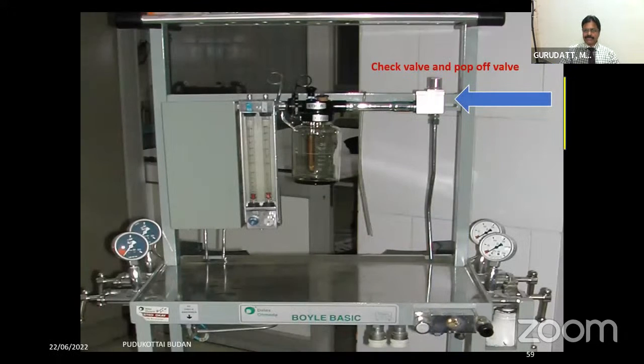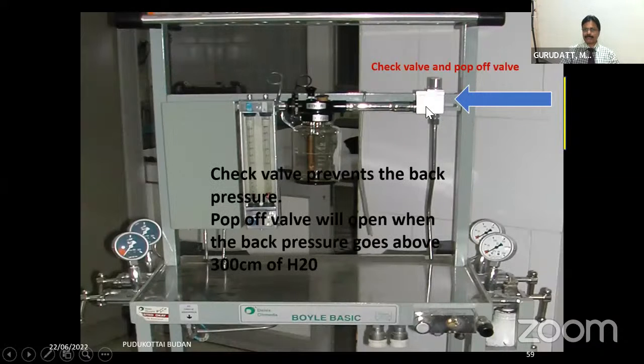After the back bar, in the majority of older anesthesia machines and also modern GE machines, we have a check valve and a pop-off valve. This check valve is again important. Whenever we start ventilating the patient, a back pressure is also created. If there is no check valve, this back pressure can enter into the vaporizers, and the problems of pumping effect and pressurizing effect can alter the outlet concentration of the vaporizers.